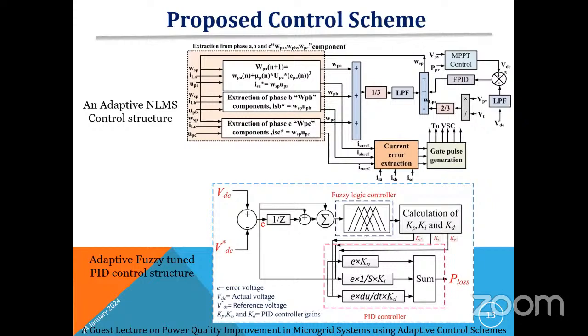Am I audible to all? Yes, sir. Yeah. So how much do we have to maintain? That is actually a very important thing. If you are supplying 450 volt AC from the grid side, how much DC voltage do we have to maintain at the DC bus terminals? Approximately.